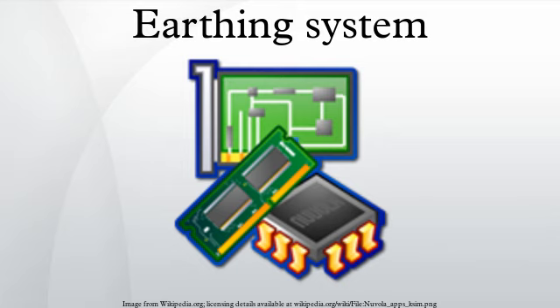The alternative is defense in depth, where multiple independent failures must occur to expose a dangerous condition. Reinforced or double insulation come into this latter category. In contrast, a functional earth connection serves a purpose other than shock protection, and may normally carry current. The most important example of a functional earth is the neutral in an electrical supply system. It is a current-carrying conductor connected to earth, often, but not always, at only one point to avoid flow of currents through the earth. The NEC calls it a grounded supply conductor to distinguish it from the equipment grounding conductor.